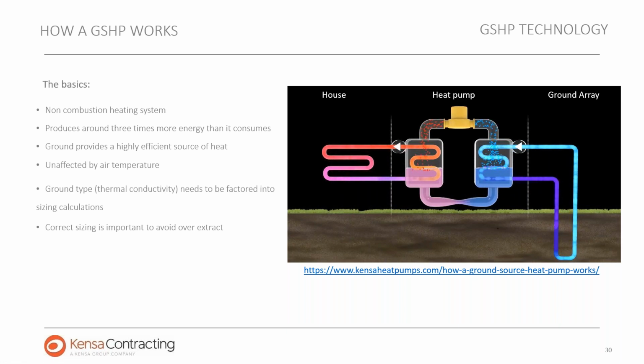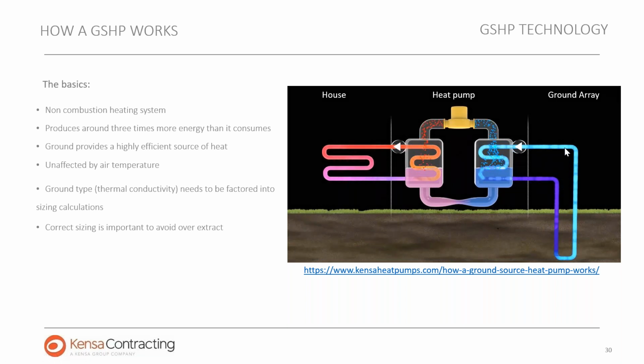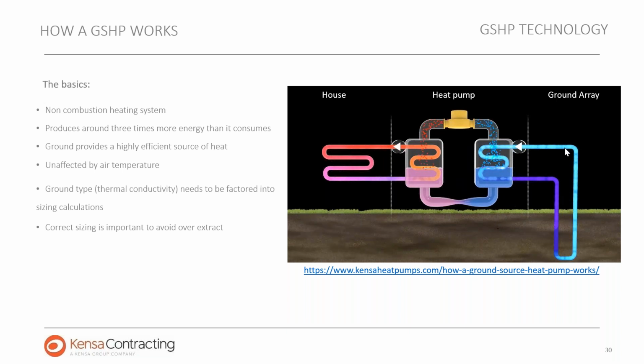Within the borehole we have HDPE pipe inserted in a loop, which eventually connects to the individual heat pump within the home. Inside that heat pump you can see the internals - on the right-hand side is the first heat exchanger, shown in blue. Our fluid, glycol, which is essentially antifreeze, runs through the pipework in the borehole, capturing the natural low-grade heat within the earth, typically between 10 and 12 degrees centigrade. That low-grade heat passes into the first heat exchanger on the right-hand side of the heat pump, changing the state of the sealed refrigerant within the unit from a liquid to a gas.